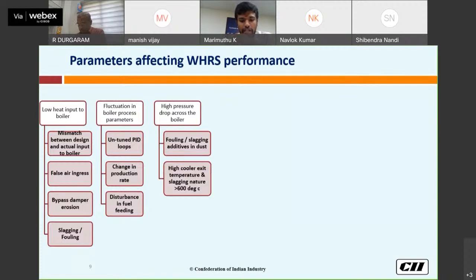And high cooler exit temperature and slagging nature. Based on the study conducted in the 6 units, we did not find the temperature to the WHRS greater than 600, so we did not identify any slagging or fouling nature dust in that boiler. But in one of the units we observed the temperature greater than 600 degrees centigrade, where the slagging has occurred and it has caused a high pressure drop across the boiler.